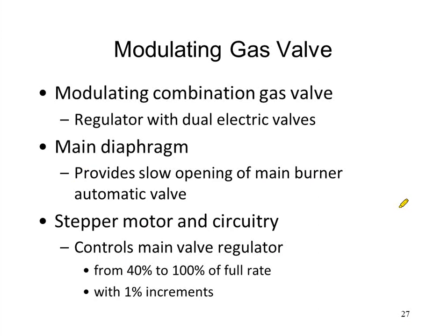I know some folks like to say, oh, well, isn't the factory the one setting up the gas valve? And they do, but they set it up at their factory, which in this case is Indianapolis, which has a different gas supplier than you have, and the gas has a different caloric value than we have here, so it's not exactly matching what we have. So you do want to use your combustion analyzer to set up any furnaces or boilers or any other gas appliances that you are using in this area.